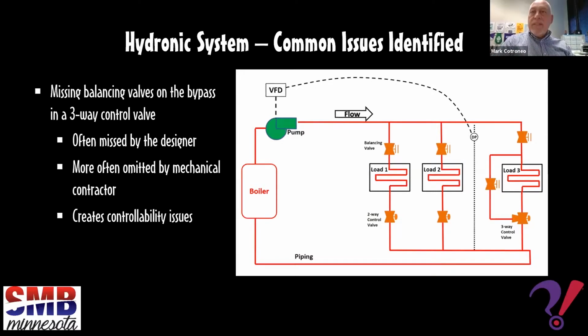It would be nice to have PT plugs at each individual coil. Quite honestly, if there's a balancing valve there, that's what we'll use. We wouldn't use these other means unless there's no other way to measure it. So it's belts and suspenders, probably. We would just use the balancing valve, and we would rather have the balancing valve. That's a calibrated piece of equipment that should probably be used.